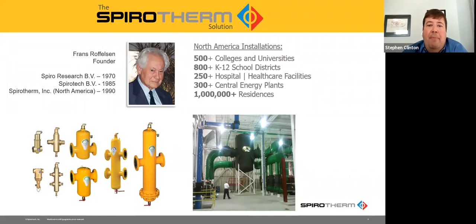Air in a hydronic system is very, very expensive. Oftentimes we may look at it and not think of the issues it causes, but there are three main issues that air causes in these systems. One is corrosion. Our industry does a decent job oftentimes of looking at corrosion, but oftentimes that's just dumping some chemicals in a pot feeder and going away for 6 months to a year. That corrosion causes all kinds of issues we're all aware of.